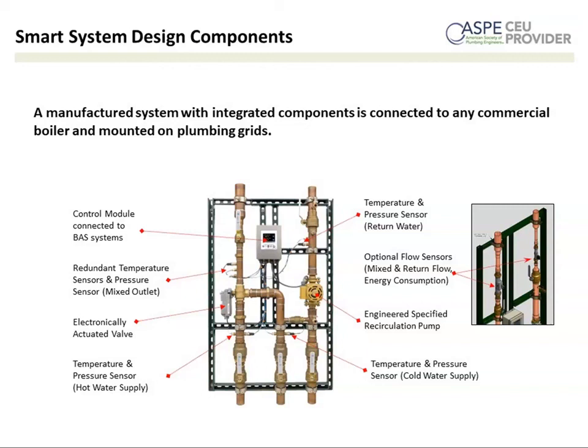So in terms of critical components, obviously the controller, which you can see in the upper left. There's sensors all throughout the system. So we're looking at mixed outlet temperature. We're looking at mixed outlet pressure. The system can also monitor the inlet hot and cold supply temperatures and pressures. There's a temperature and pressure sensor on the return. And then there's the pump, which is optional. Most units, if there's a pump that already exists, can tie into the unit, but their pump can be specified and built right into the unit if that's required.